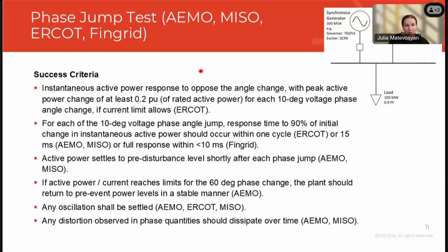And in the criteria, what they're looking for is instantaneous power response to oppose the angle change for each of this 10 degree voltage phase angle change, as long as current limit allows. There is a definition, as I mentioned, for the 90% response time. So this is what's being looked at in the tests.